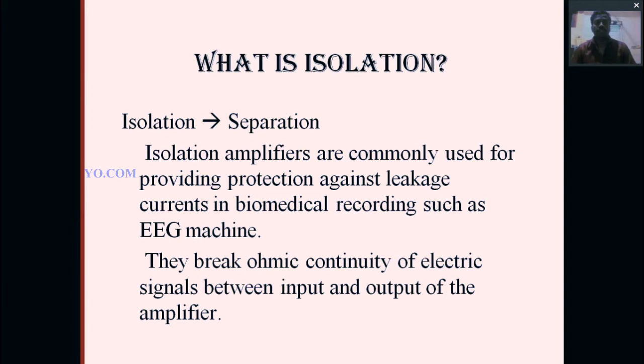Separation is also called isolation. Isolation amplifiers are commonly used for providing protection against leakage current in biomedical recording such as EEG, ECG, etc. They break the ohmic continuity of the electric signal between the input and output of an amplifier.